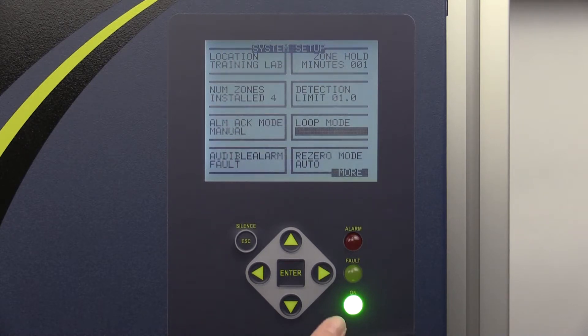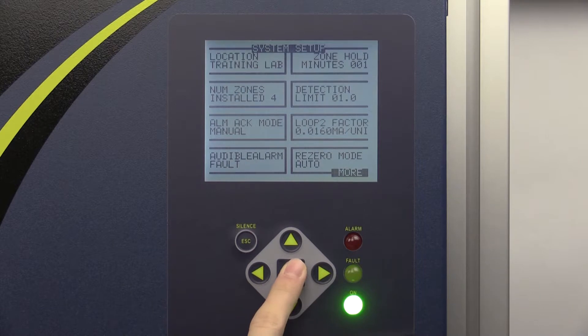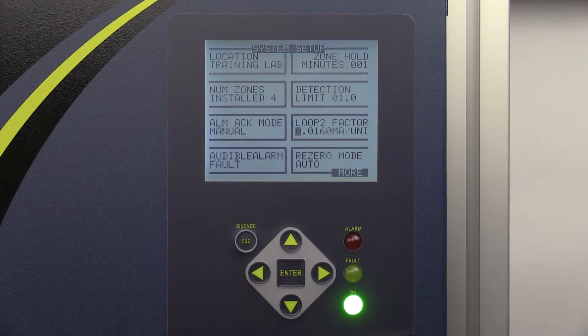Press enter twice on the loop mode tab to access the loop 2 factor tab. The loop 2 factor sets the PPM scale factor for current loop number 2. If you want to calculate the current output, multiply the scale factor by the current PPM reading and add 4.